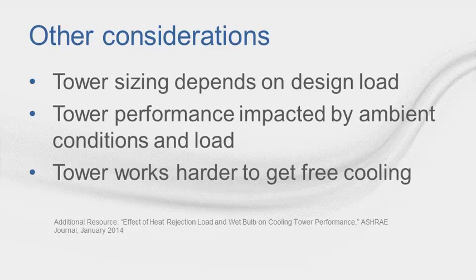A few things that must be kept in mind: the tower must reject the heat of compression in addition to the design cooling load — this is what it will be sized for. When the plant operates in free cooling mode, the building is not typically going to be at design load and ambient conditions are cooler. Tower approach increases as outdoor air wet bulb decreases, and tower performance is also based on the cooling load. As a result, the tower may need to work harder to get free cooling.